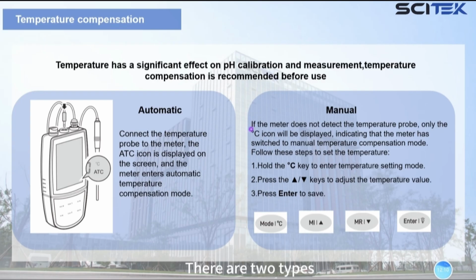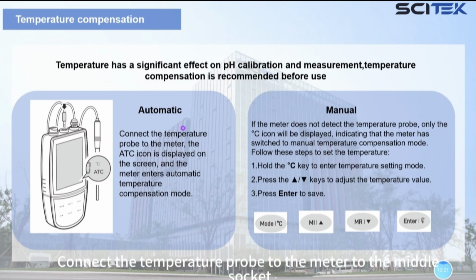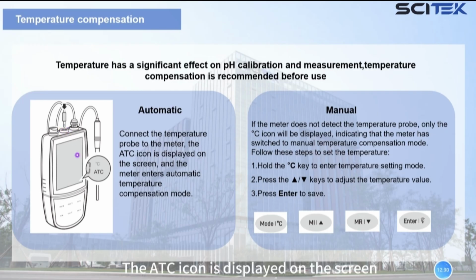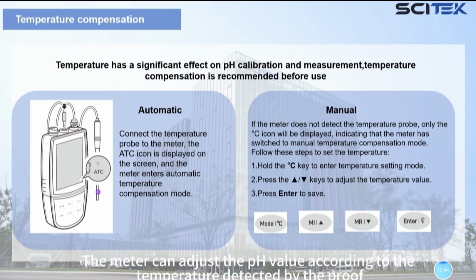There are two types: automatic temperature compensation and manual temperature compensation. For the automatic type, connect the temperature probe to the meter, to the middle socket. The ATC icon is displayed on the screen, and the meter enters ATC mode. Put the temperature probe into the buffer solution, and the meter can adjust the pH value according to the temperature detected by the probe.